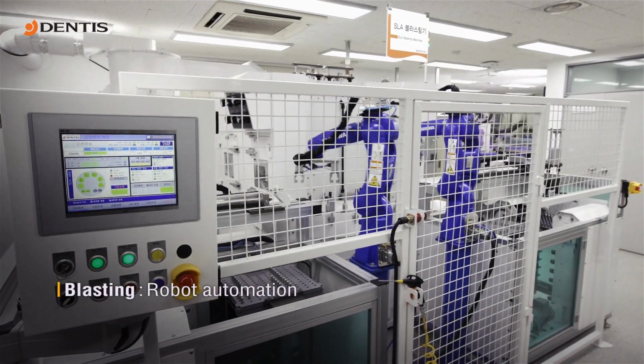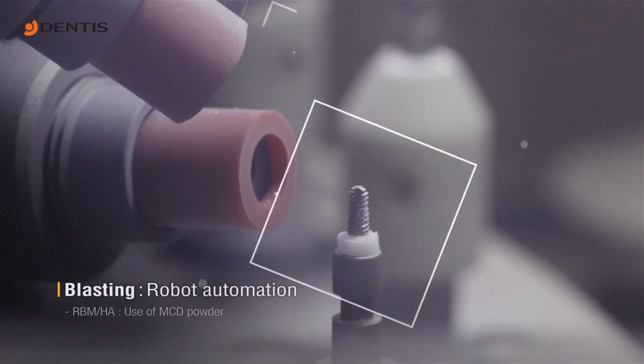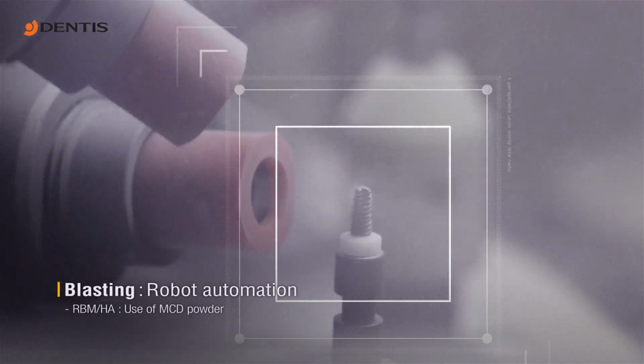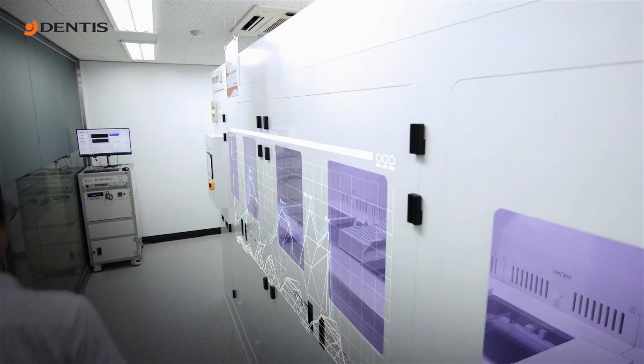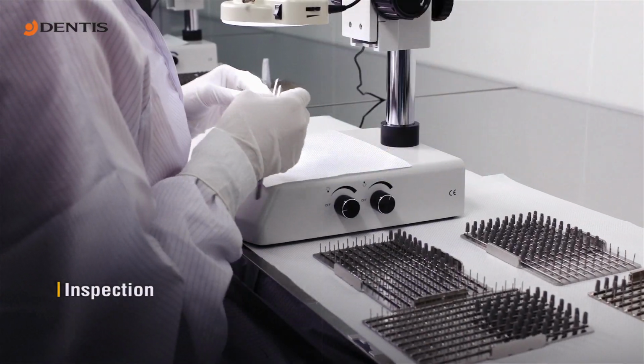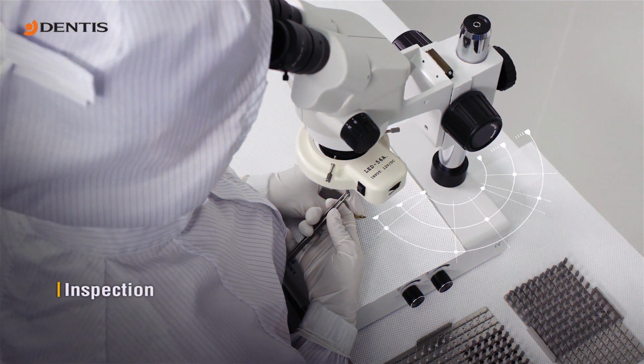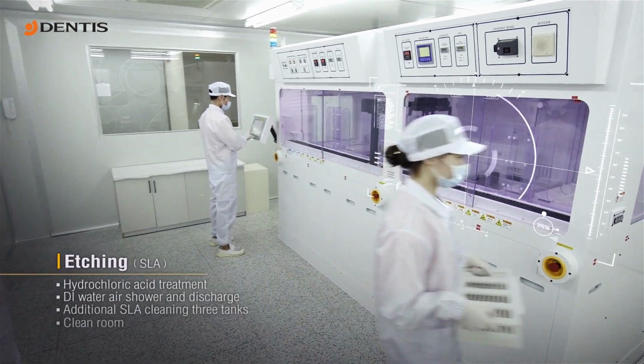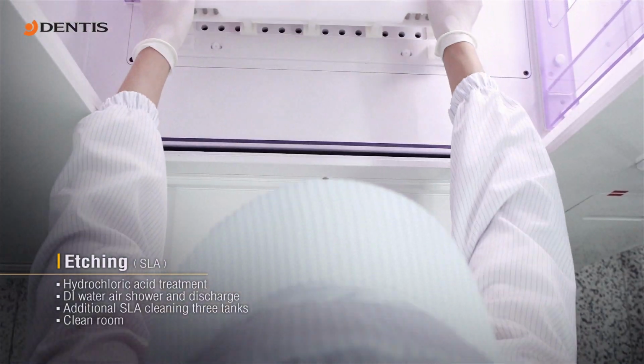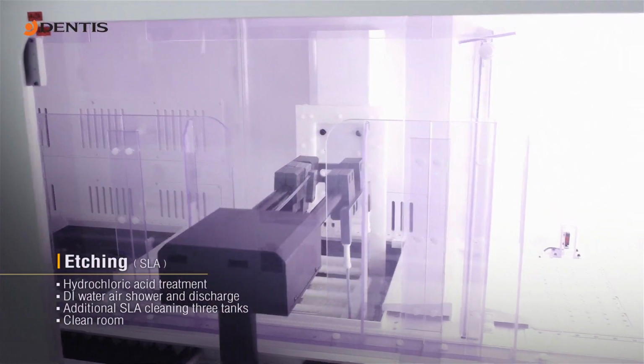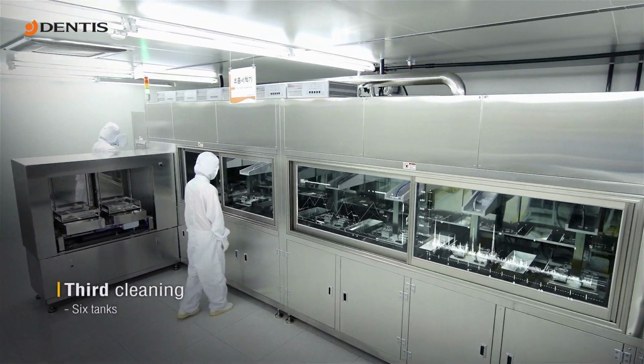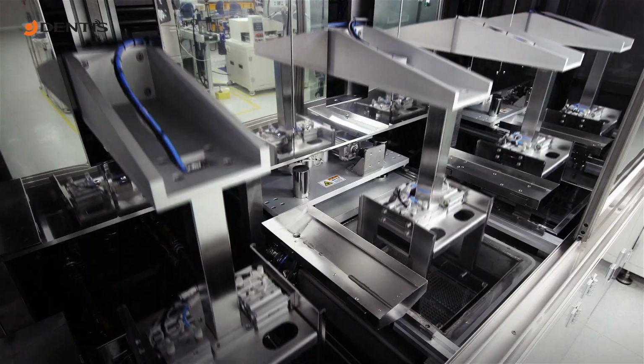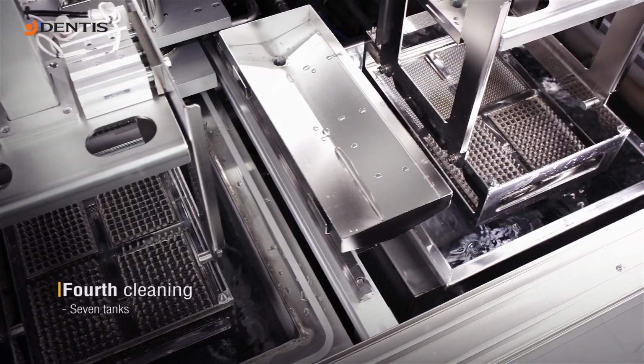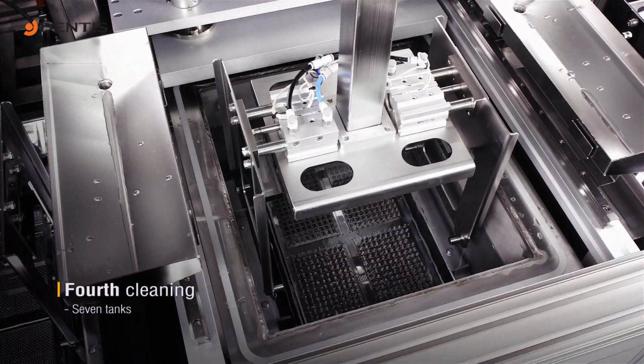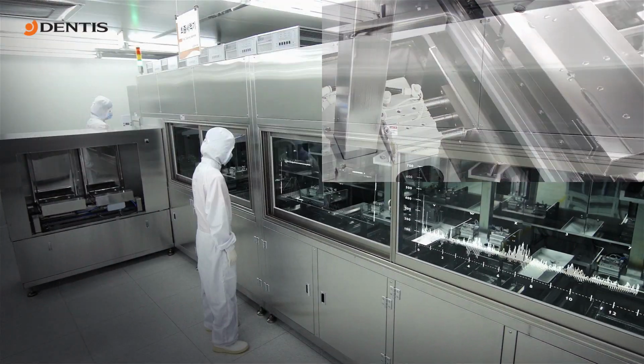The next step, blasting, makes the fixture surface rough. Automated robots ensure precision in blasting of the implant surfaces and monitor and inspect the surfaces in real time. SLA products undergo an additional cleaning in 3 tanks to etch the surfaces and remove acids. Implants that have gone through the surface treatment undergo a 13-step cleaning process that consists of cleaning in 6 tanks in the quasi-clean room and cleaning in 7 tanks in the clean room.